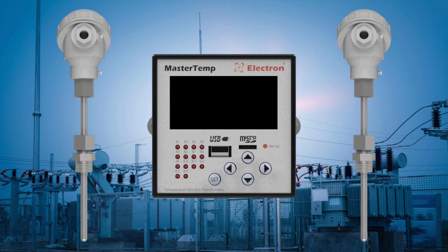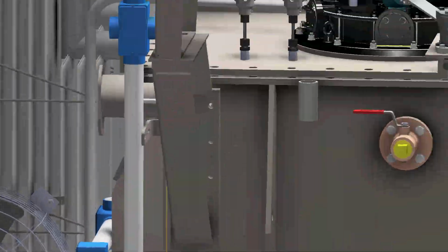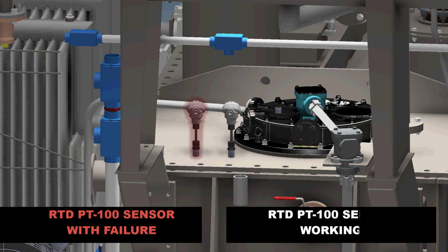The two PT100 sensors of the Mastertemp can also be configured to work in backup mode. That is, the two sensors at the top of the transformer, if any of them fail or present any defect, the other sensor assumes monitoring while maintaining the integrity of the thermal image calculation and monitoring the temperature of the oil top.